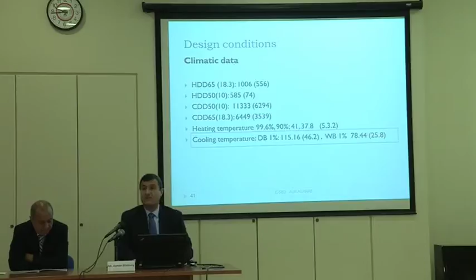Now, how will the AC perform at high temperature? What happens if we make it 46 or 48? Those in the air conditioning business know that it has a big effect on the EER and on the kilowatt per ton efficiency of the machines. Let me be clear about definitions. Going back to my class, what we mean by EER values: EER is capacity divided by power, but the units are different. We speak about BTU per hour for the capacity, and watts for the power of the compressor. But some countries use kilowatt per ton, which is another SI unit, meaning the same thing. There is only a conversion factor between the two.